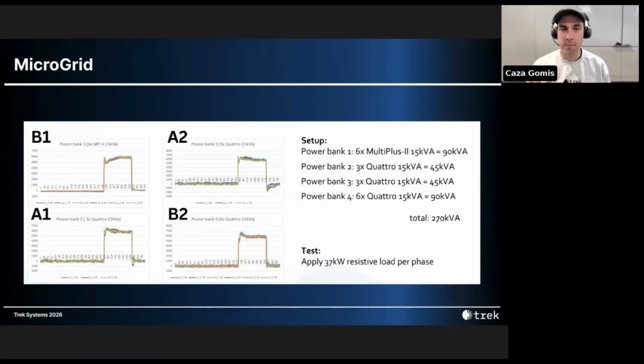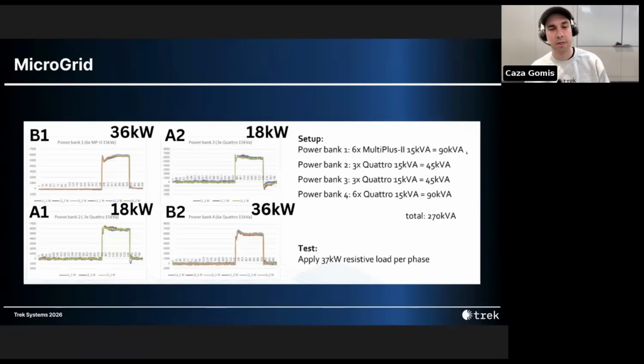They set up 4 power banks to support a 3-phase system. 2 power banks rated for 45 kVA. These are represented in graphs A1 and A2. And 2 power banks rated for 90 kVA, graphs B1 and B2. You'll notice that the main difference in these graphs is the number of colored lines, where each line represents a single inverter. So you have 3 inverters in each A graph and 6 inverters in each B graph. They then applied a 37 kilowatt load to each phase. So that's about 111 kilowatts in total.